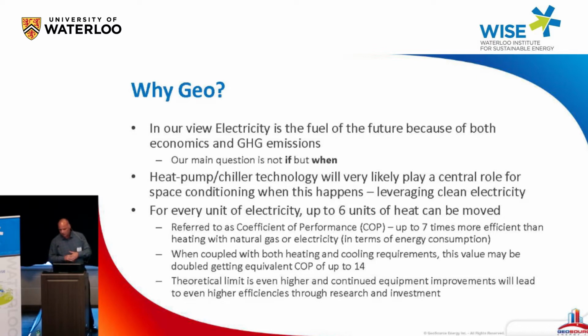That's where we get our economics, certainly on the cooling side—cooling is fantastic with geo because of low ambient temperature. One example is Ball State University, which has a very large district geo system where they're getting COPs of up to what they call 14. They're kind of double counting, but there are buildings that require cooling and others that require heat, so they get this very high efficiency because they're simultaneously doing heating and cooling using the same compressor or chiller.